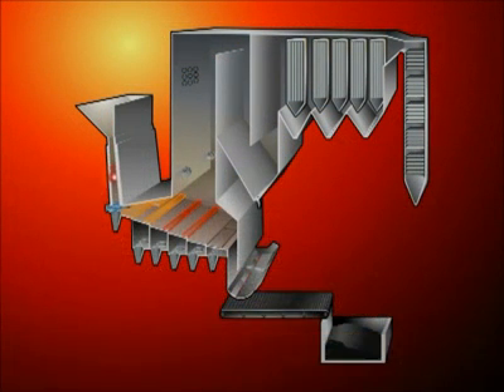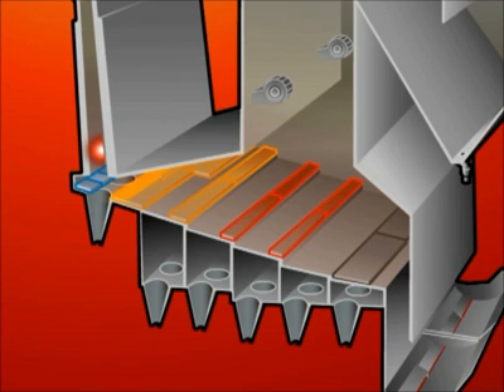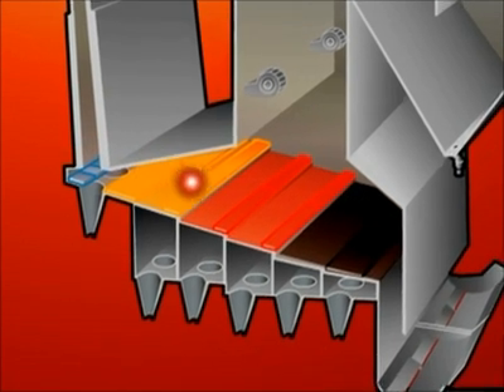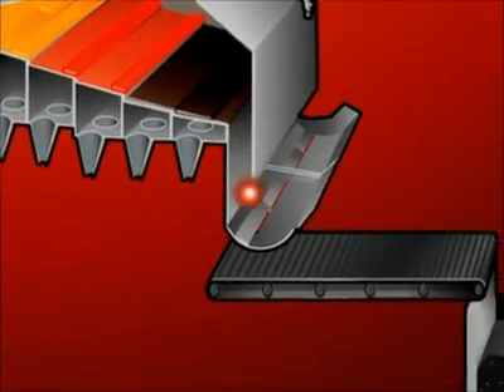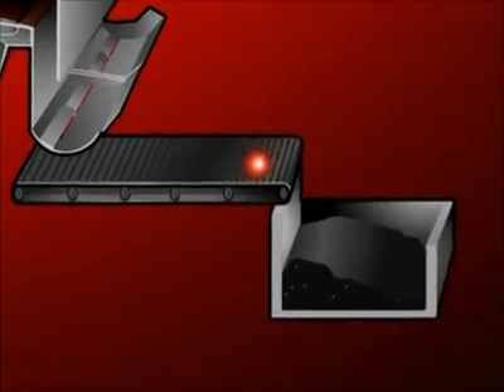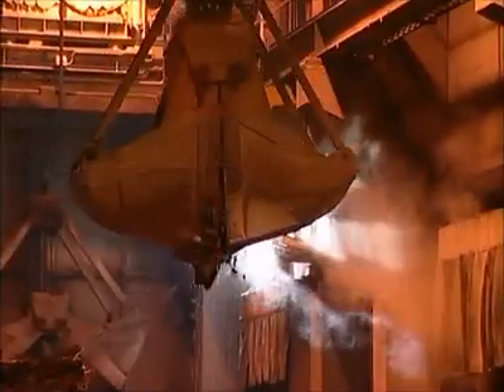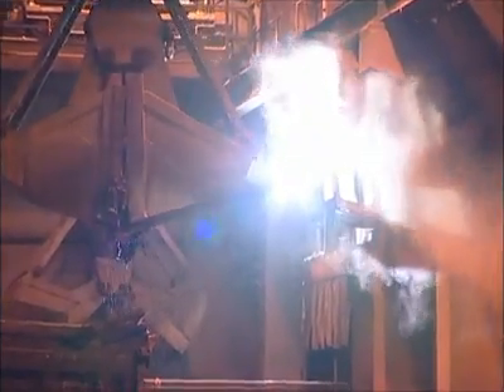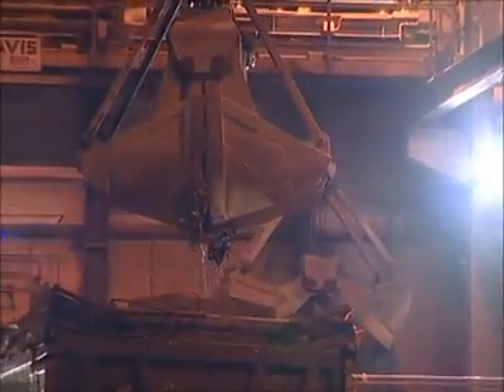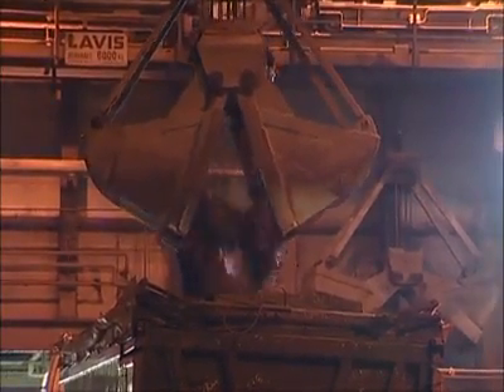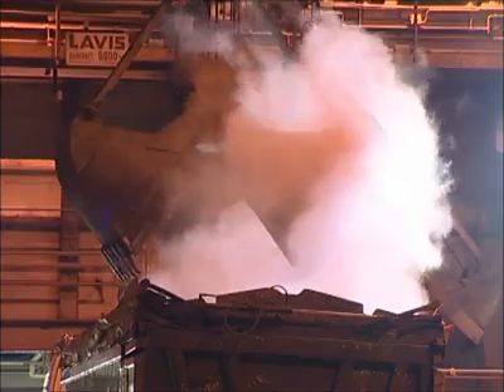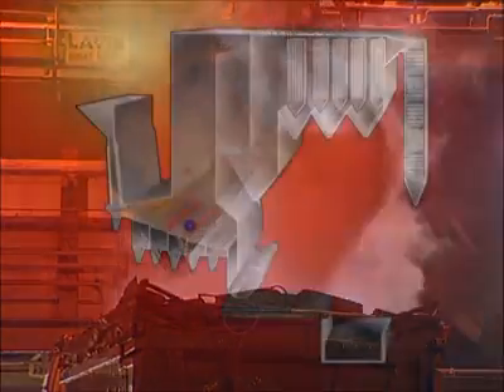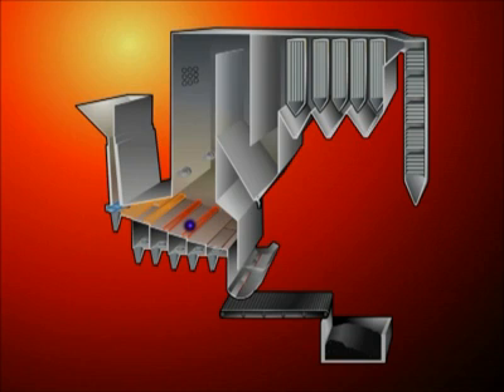The fuel then proceeds through the shaft down to the feed table, where hydraulic pushers feed the fuel according to the power requirement. The grate boiler comprises a drying zone, a combustion zone and final combustion. When the material is burnt out, the residue or clinker drops into the clinker extinguishing vat, after which it is fed into the clinker bunker. The clinker is then taken to a disposal plant where it's recycled. The scrap is separated off using a magnetic separator, and the residue replaces virgin material for covering and wall construction at the disposal site.